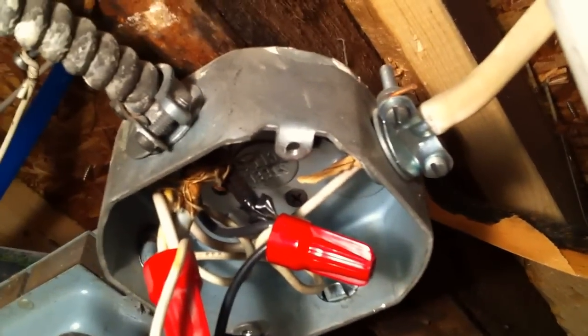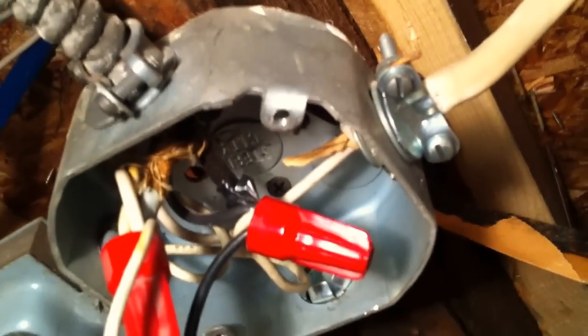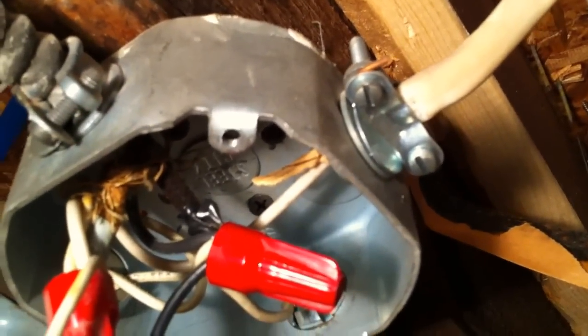A grounding screw should be used to connect the equipment ground of the NM cable to the metal box, or some other type of listed grounding device. You're not supposed to take the equipment ground and wrap it around the clamp screw as they did here. This is Russell Blank, NEC consultant for EC&M magazine.